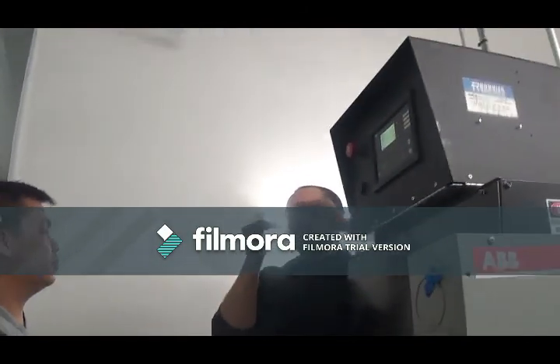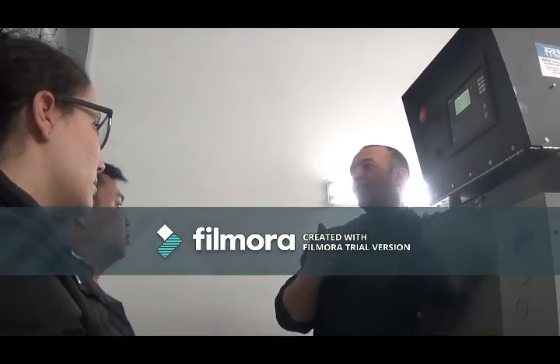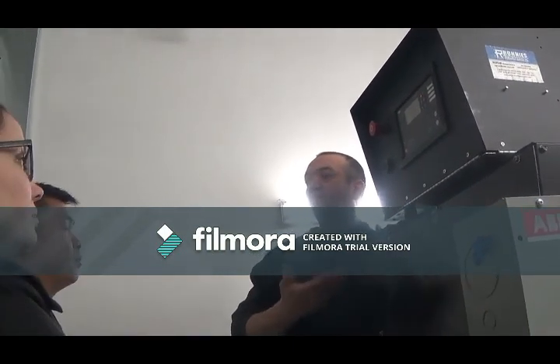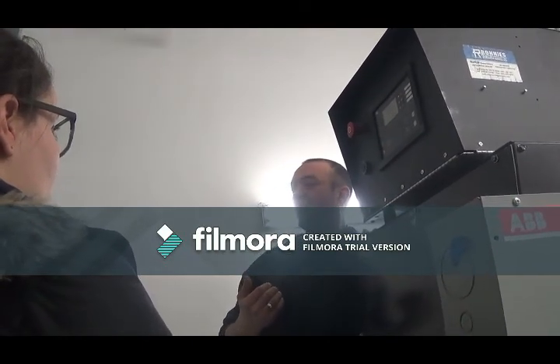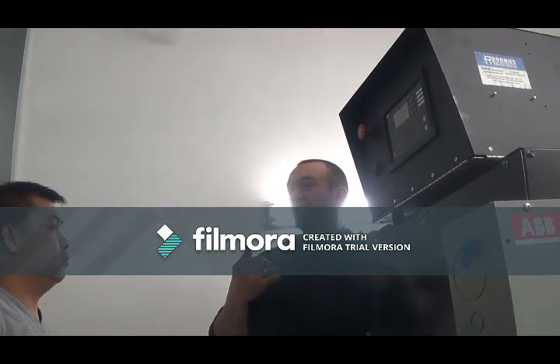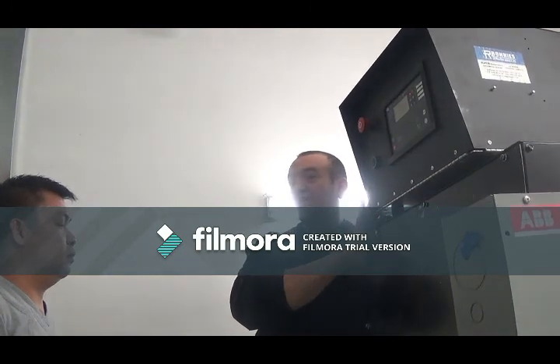60.2 is okay. You always get that. It won't go up to 61. Even 61, if there's a percentage, even 61, if you see it 63 and up, then you gotta let us know, because at that point you're starting to cause damage in the equipment. If you see it at 56, 55, you let us know when the generator does not start, because if you have over speed or under speed, it's already set up to shut off by itself.